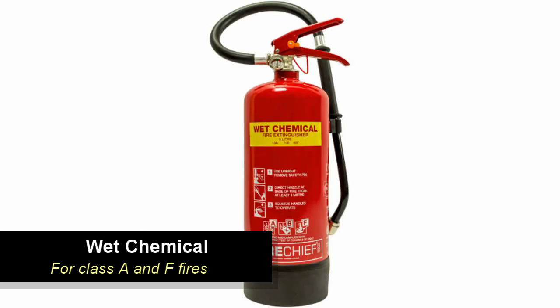Wet chemical extinguishers work by forming a layer of foam on the surface of the burning oil or fat, preventing oxygen from fueling the fire any further. The spray also has a cooling effect. This type of extinguisher is particularly suitable for commercial catering establishments with deep fat fryers.